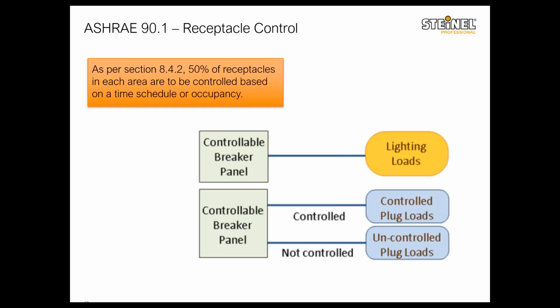The next topic that we are going to talk about would be receptacle control. So ASHRAE 90.1, all the different versions or releases of it, requires receptacle control. As per section 8.4.2, 50% of receptacles in each area are to be controlled based on a time schedule or occupancy. And here's a little diagram that shows how this is going to work. So you have your lighting loads that are controllable, and then you have controlled plug loads and uncontrolled plug loads.